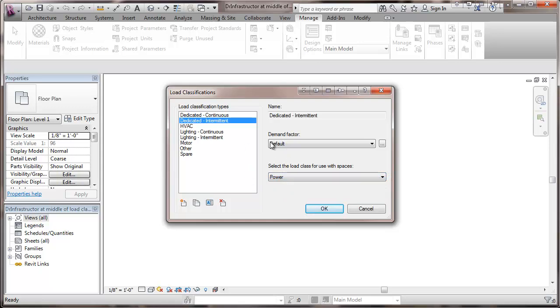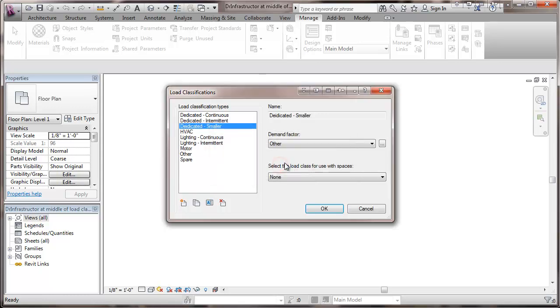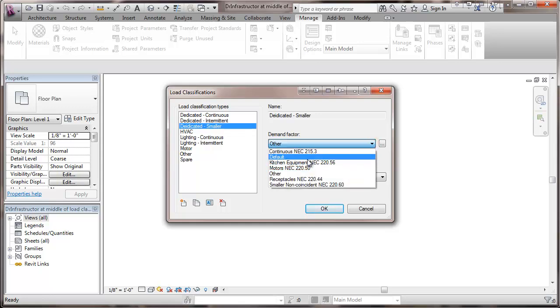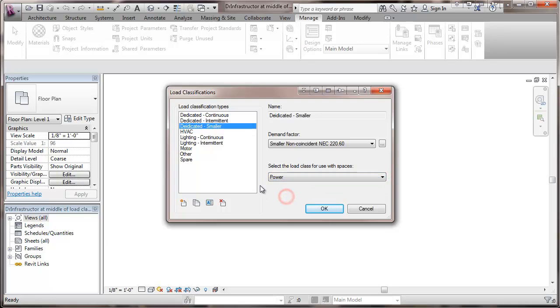Now I'm going to add something a little different here with a dedicated smaller. And this is for a type of equipment where you have two pieces of equipment that are installed and they can't possibly because of interlocks run at the same time. So the electrical code allows us to use a smaller non-coincident load rating here which you wouldn't calculate the load for the smaller piece of equipment that couldn't run. And we're going to call this power as well.